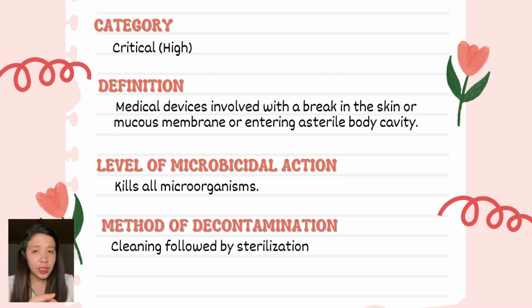So for the first category, let's talk about critical or high. These are medical devices involved with a break in the skin or mucous membrane or entering a sterile body cavity. For the level of microbicidal action, it kills all microorganisms. For the method of decontamination, cleaning followed by sterilization, usually heat if heat stable or chemical if heat sensitive.